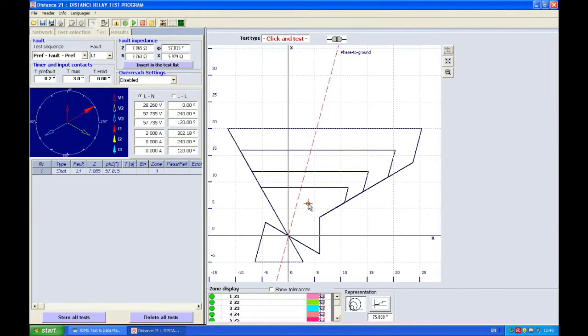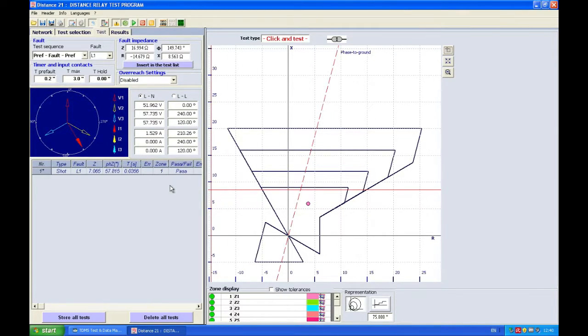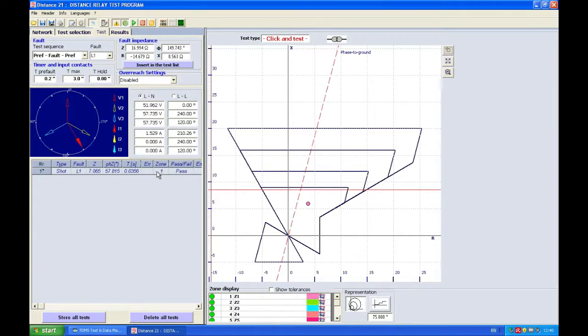So I see my relay tripping and you can also see the relay tripping here because you can see that the tripping time is 35.6 milliseconds. That's zone 1 and that's a pass.